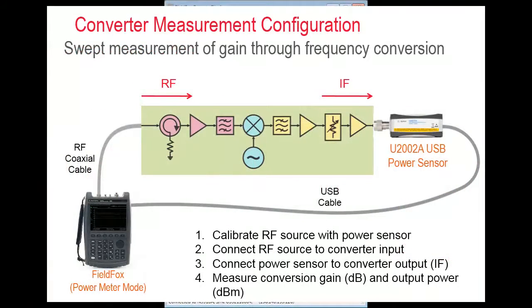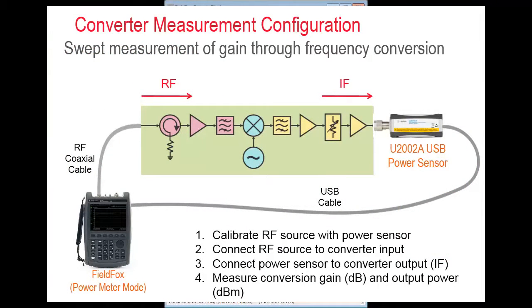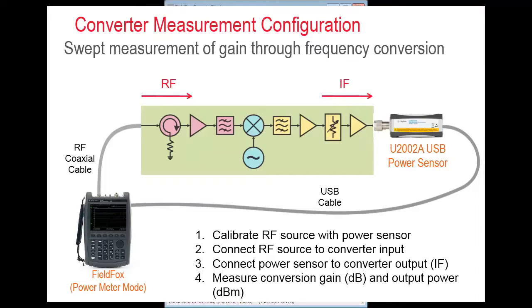The diagram shown here presents the basic idea behind measuring frequency converters using FieldFox option 208, which enables you to make frequency offset measurements using a power sensor or FOPS.